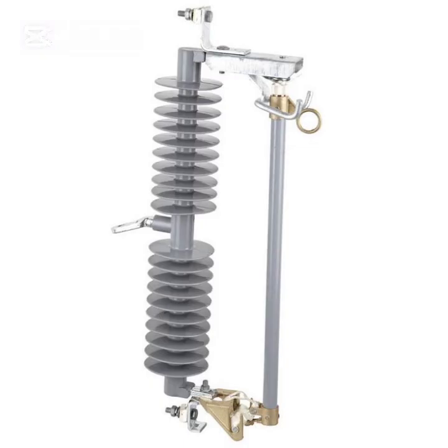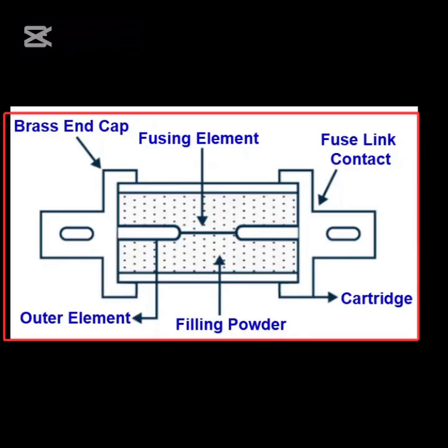2. Fuses. A fuse is a small wire or thin metal strip that melts when an excessive current passes through it for a certain period. It is connected in series with the circuit it protects. During normal operation, the fuse remains below its melting temperature and carries the load current without any issues. However, in the event of a short circuit or overload, the current exceeds the fuse's rated limit, causing its temperature to rise above its melting point and blow the fuse.